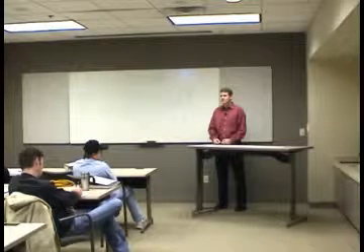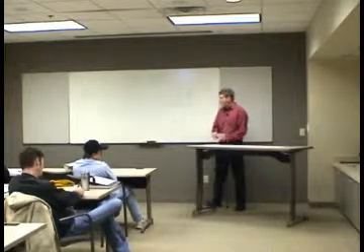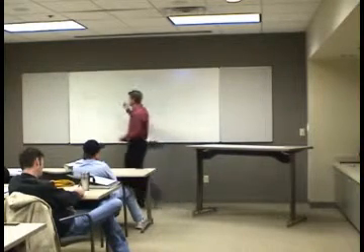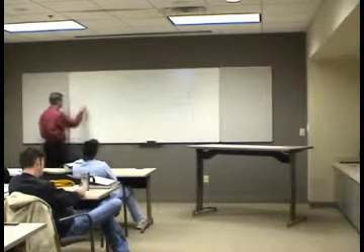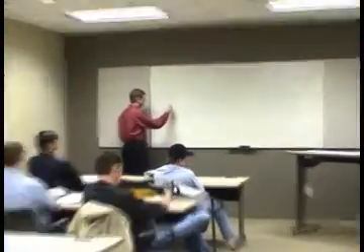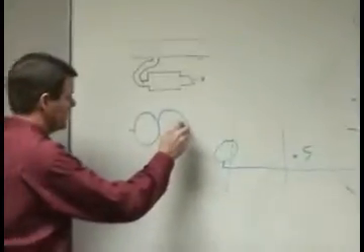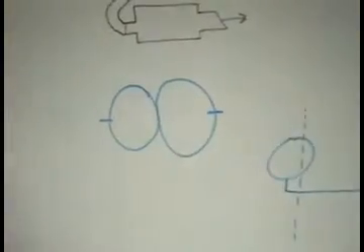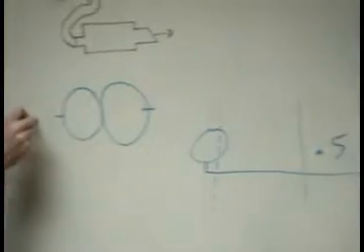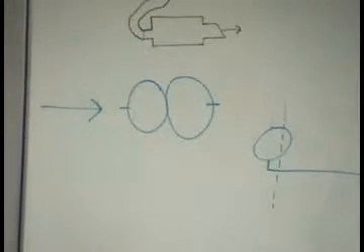But if you have a discharge air sensor, you can control it, watch it, and maintain that delta T, which will give you a better mix within the room, and your thermostat no longer becomes an altimeter, it becomes actually a temperature sensing device, because you're getting a better mix in the room. There have been lawsuits, and engineers have been cleaned up like you can't believe, because they don't know that one particular little phenomenon. They keep putting more and more heat into it, and the room gets worse and worse.